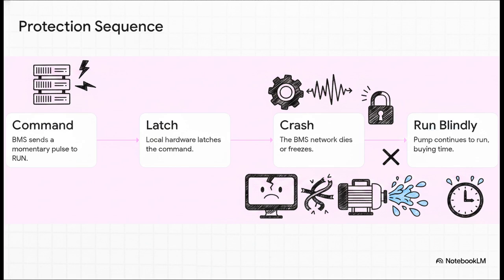The network is completely dead. But look at step 4. Because the command was latched locally in the hardware itself, the pump completely ignores the dead network. It just keeps running blindly. This local hardware insurance keeps the cooling water flowing and saves the servers, buying incredibly valuable time for the facility engineers to sprint to the room, figure out the fault, and manually override the equipment.